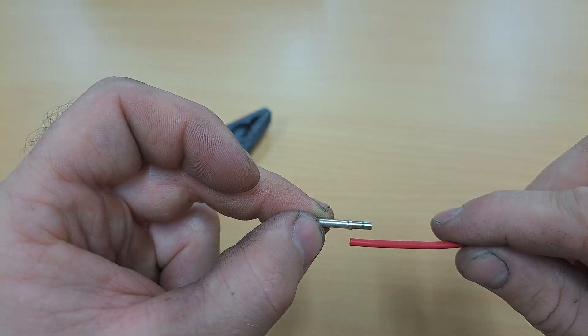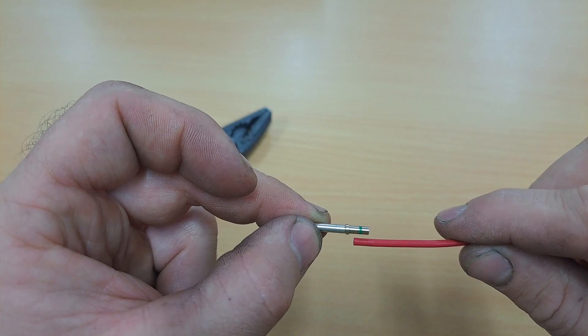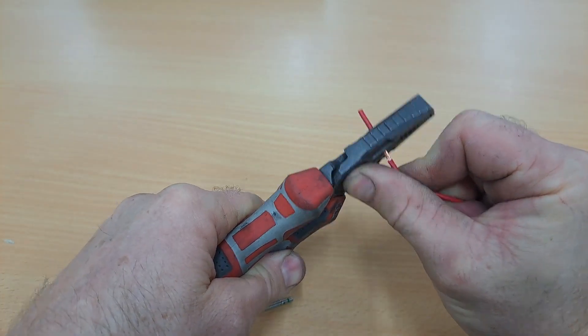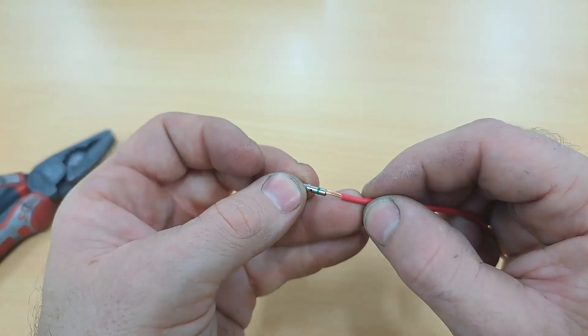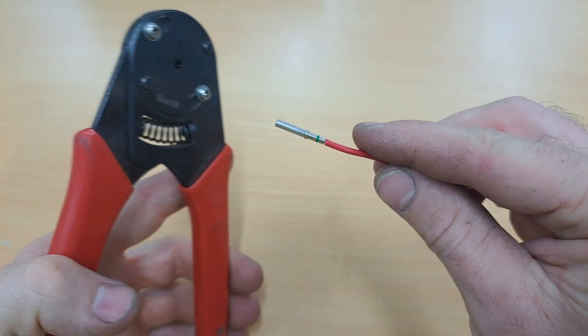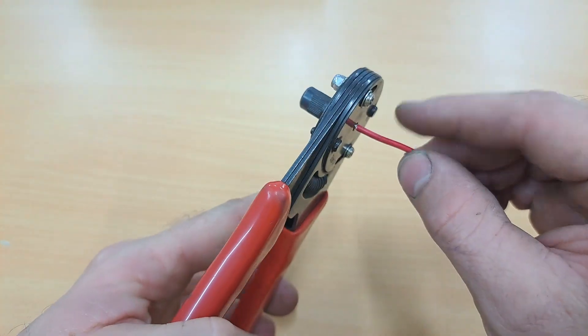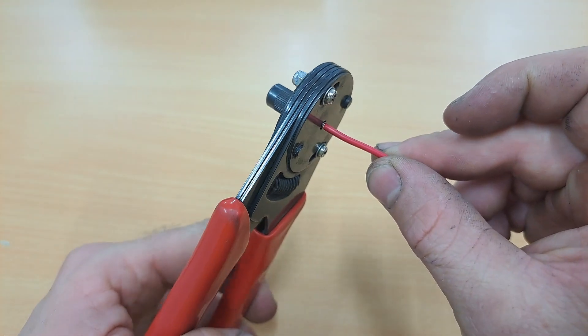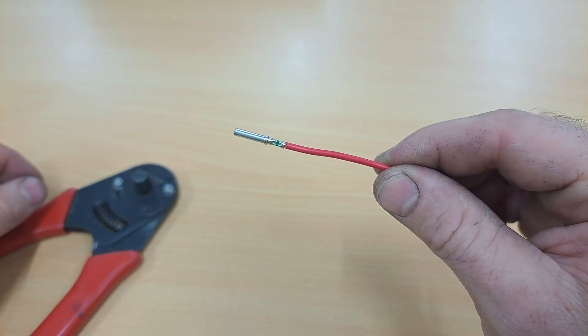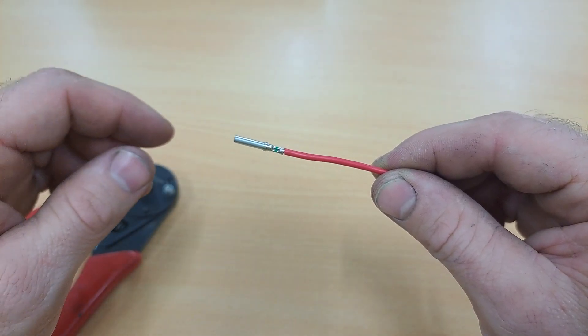We want to strip the cable to take up the whole space of the green striped area. Now get the crimper and crimp the connection. Make sure it goes all the way in. Once it is crimped pull on it to make sure that it is firm and in place.